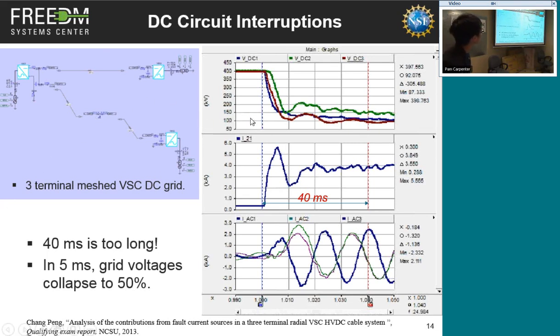I was saying, at 5 milliseconds, if you look at the simulation results here, the system voltage dropped to about 200 kilovolt. That's 50%. So consider you are controlling your voltage source converter, and the voltage dropped to 50%. I think it is very difficult to maintain the normal operation of your converters, especially considering that you are trying to transmit power from AC to DC. So the conclusion is we're talking about a few milliseconds. That's our target.